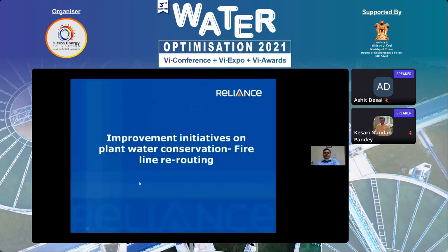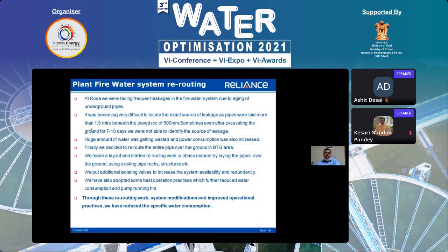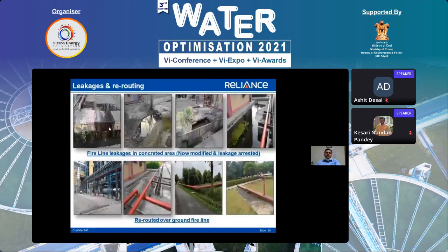These are the improvement initiatives on fire water line rerouting. I have earlier mentioned that there were a lot of leakages, and they were 1.5 meters beneath the paved RCC of 500 mm. Recently our management, which is very kind and supportive of water resources, approved this. You can see the concrete peaks, beneath which there was a leakage. That has been nullified, and we have rerouted the line overhead instead of underground, and now there is no leakage of fire water. It is a very critical auxiliary for the fire hydrant, so it has to be maintained in good shape to avoid problems during a major emergency.